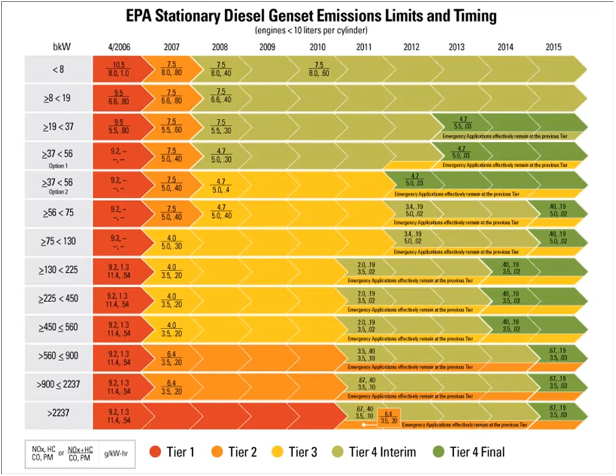From a healthcare perspective, the definition of what constitutes these emergency engines is probably pretty important. Emergency, in the EPA's eyes, effectively means the engine should not be required to run except when the normal source of power fails, whether that's a fault with an incoming substation or a statewide blackout—once that happens, there's no limit to how long emergency engines can run. But for non-emergency purposes, such as maintenance and testing, there's a limit of 100 hours per year, unless a local code or regulation mandates otherwise, and the operator is required to record all use referenced to the engine hours meter.